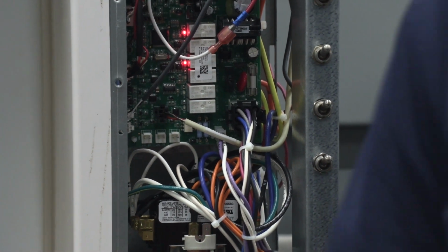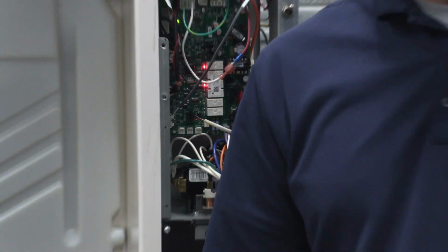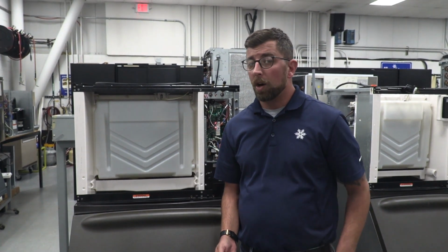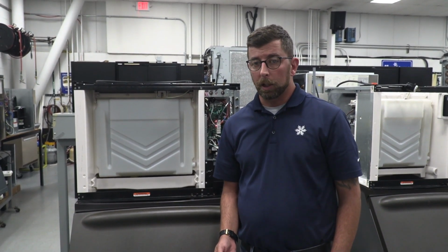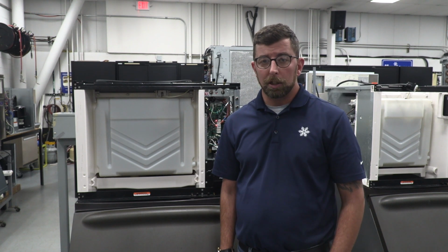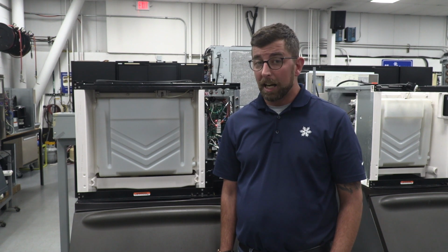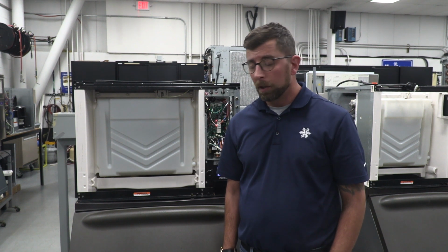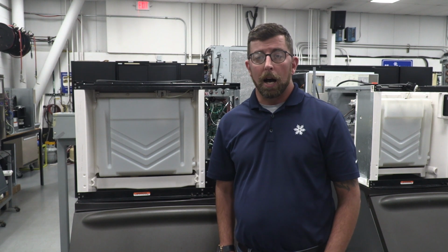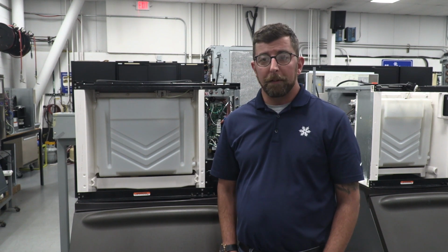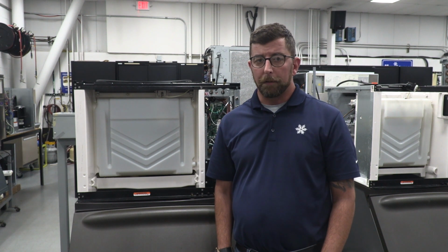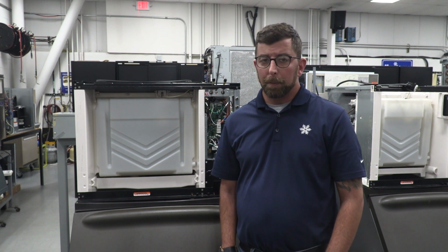So everyone, that tells us one of two things. My board is calling for water and I'm not getting water right now. So either I don't have water coming to this ice machine, which if you have a water filter with a gauge on it, two things you want to check there. What is my standing water pressure, my static pressure? Let's go ahead and turn this thing off since we're not going to make ice anyway. See where I'm at. So if I'm at 50 psi, see what happens when the water valve turns on. If you drop noticeably, you've got a plugged water filter.